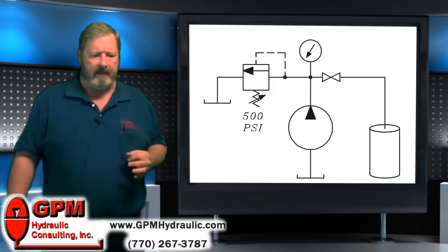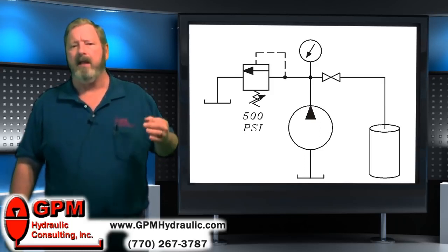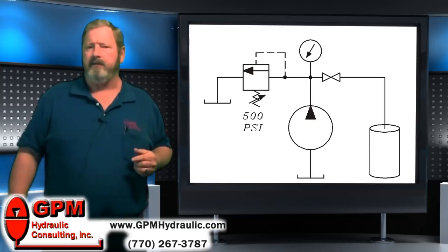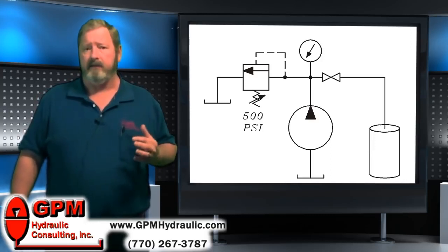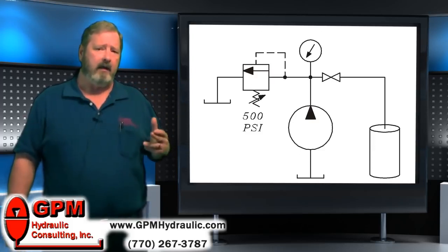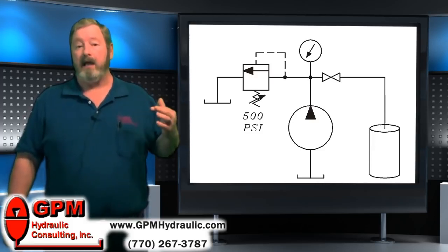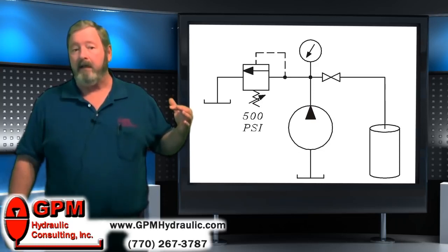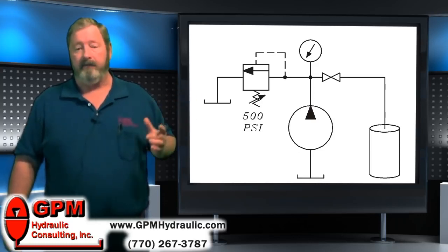On hydraulic schematics, normally closed means that it normally blocks flow. Unlike on an electrical schematic, where a normally closed electrical switch allows flow, on a hydraulic schematic, a normally closed valve normally blocks the flow and something has to happen to open the valve and allow flow.